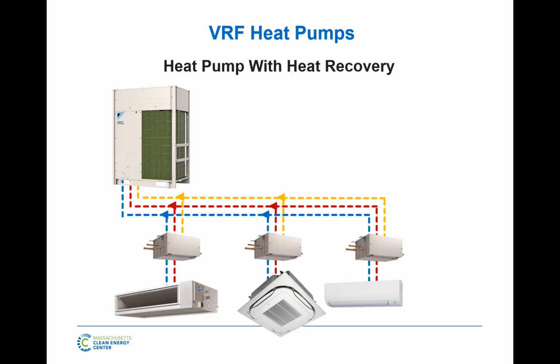Now the heat recovery system, probably the most famous VRF system, also known as the simultaneous heating and cooling system, is the one that allows each and every indoor unit to heat and cool independently and simultaneously. Now, multiple manufacturers do this by introducing a third pipe into the system. Some don't. We'll talk about that in a minute. All manufacturers do introduce another component called a changeover device, a branch selector box, a branch controller box, with different names for them. The way this works is that in this changeover device there is usually a set of valves. Sometimes it's a heat exchanger, depending. So what happens is in a three-pipe system, there's always a hot supply, a cold supply, and a common return.